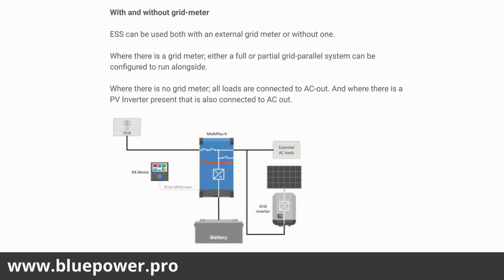So with and without grid meter, ESS can be used both with an external grid meter or without one. When there is a grid meter, either full or partial grid parallel system can be configured to run alongside the grid. Where there is no grid meter, all loads are connected to the AC out, and where there is a PV inverter present, that is also connected to AC out. So this is running a system without an energy meter.